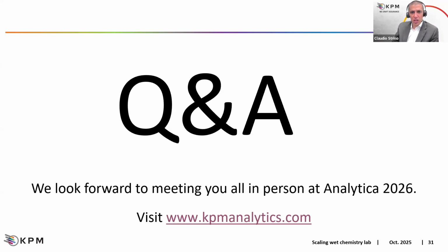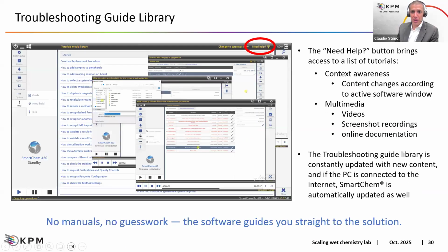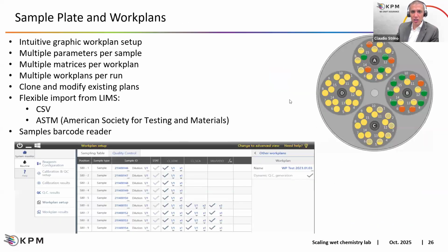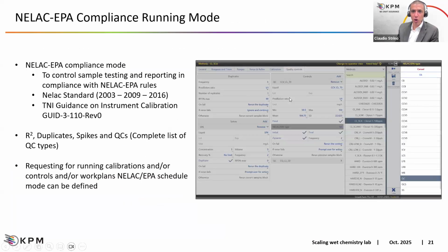We currently have 3 QCs that we have to prepare individually from our instrument. It would be great if we could just load the stock solution and tell the system to make each standard from that. Yes, this is a feature we implemented already in the software. So, instead of manually preparing the QCs, you can have QCs automatically prepared by the system starting from a standard, because we can define the name of the liquid and we can define the dilution we want to apply. So we can ask the system to automatically prepare a QC starting from a standard.